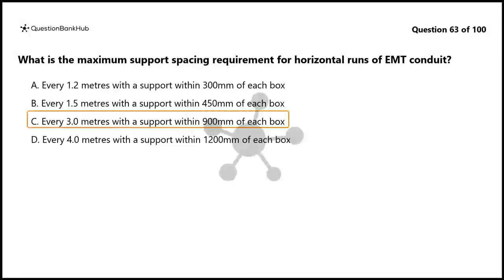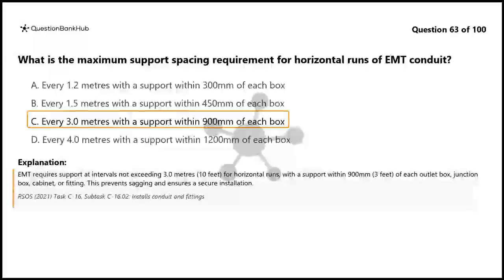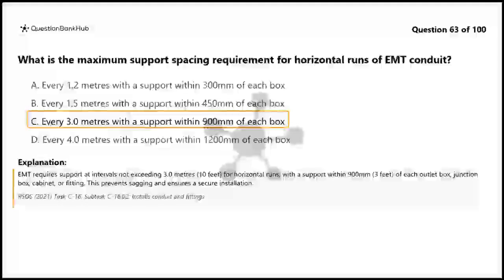The correct answer is C. Every 3.0 meters with a support within 900 millimeters of each box. EMT requires support at intervals not exceeding 3.0 meters, 10 feet, for horizontal runs, with a support within 900 millimeters, 3 feet, of each outlet box, junction box, cabinet, or fitting. This prevents sagging and ensures a secure installation.